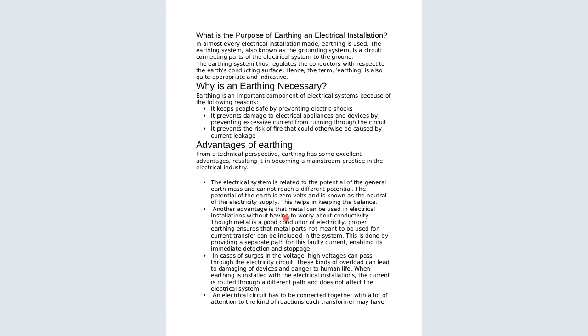Another advantage is that the metal can be used in electrical installation without having a worry about the conductivity. And this is because when earthing is done, all the excess charges will be drained to the ground and hence will not cause an electrical shock. Sometimes you do this electrical installation and you find some metallic parts or equipment in the house. Things like the showers, things like water pipes, normally most of them are metallic, but you realize that they will not cause any electric shock because the house has been well grounded. So an advantage for this earthing, it makes sure that all the electrical system equipment are connected to the general earth mass and cannot reach a different potential.